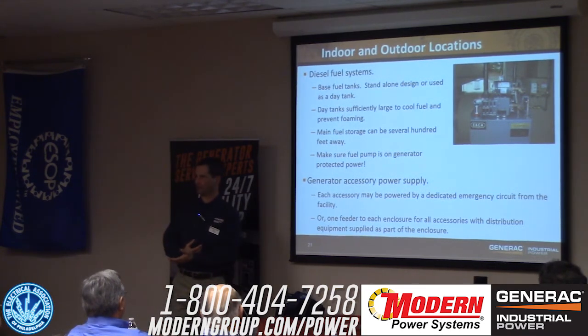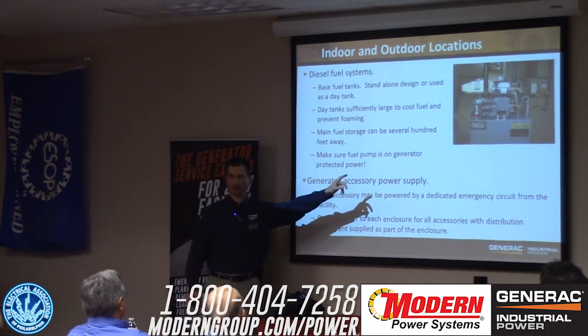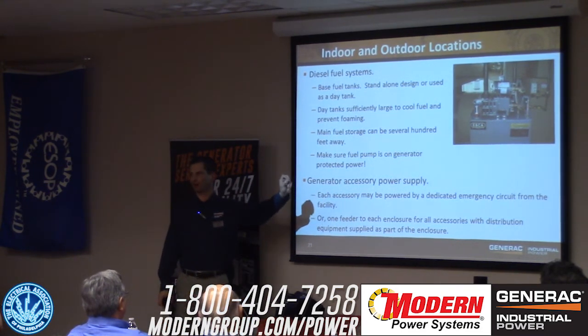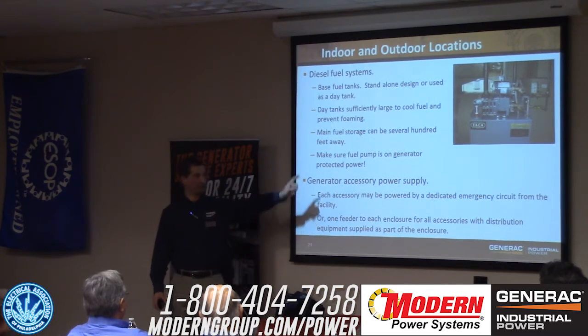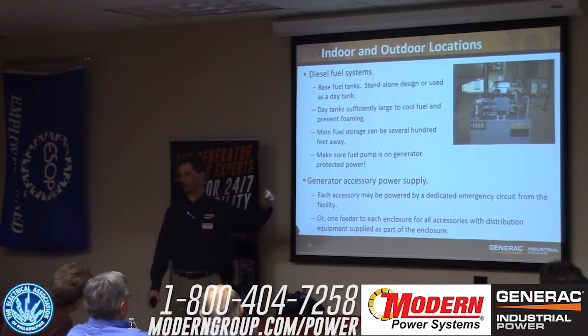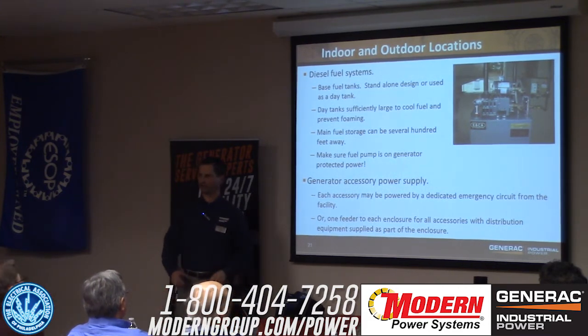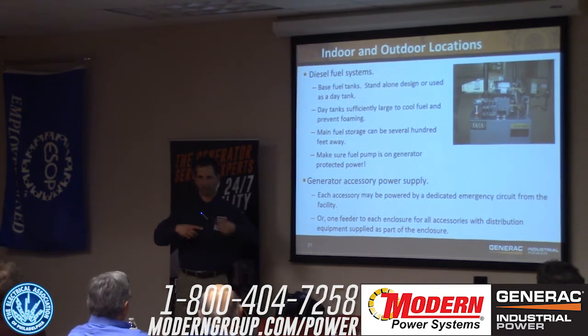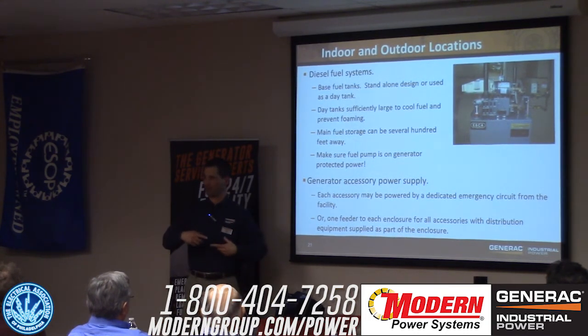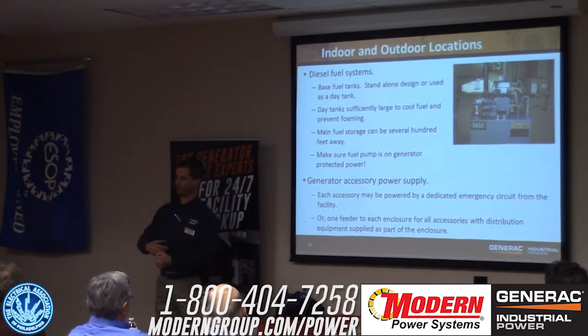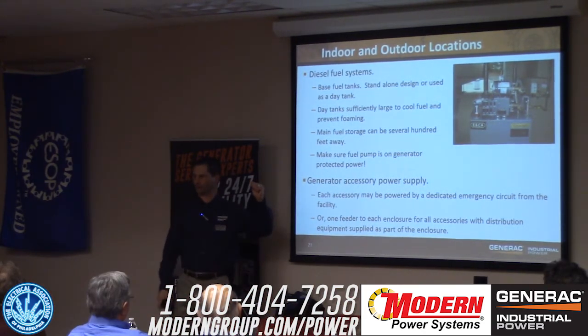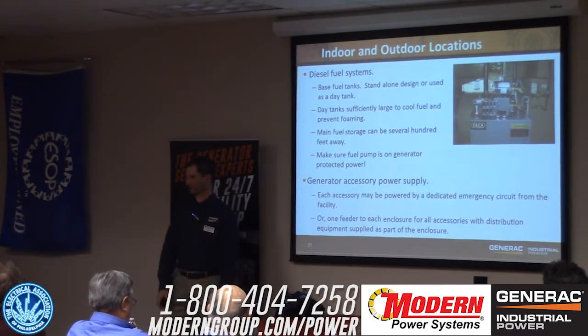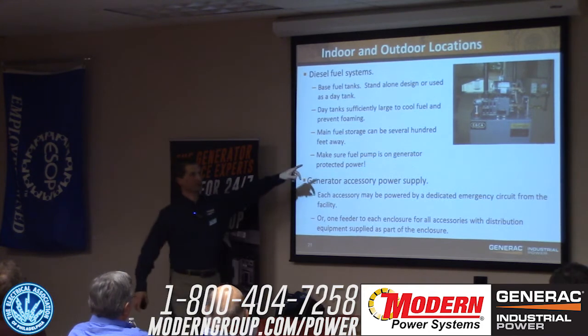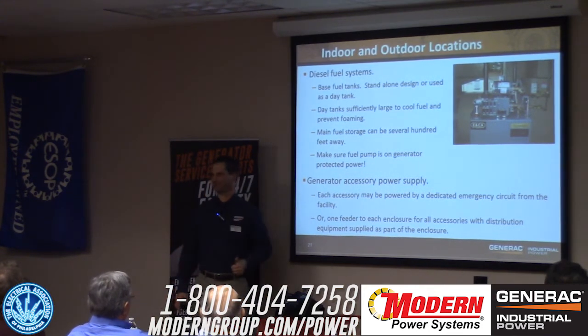If you're going to use a remote tank with a day tank, it's got to have at least 2 hours of fuel in there. So if you've got a 500 kW gen set and it's going to burn 30 gallons an hour, you want that tank absolutely no smaller than 60 gallons because the injector pump in that engine is cooling itself with that diesel flow. So it's circulating that diesel fuel, and a lot of it is being bypassed through the pump, returned back to the tank. If that tank's too small, that fuel's going to heat up. It's going to start to foam. I'm going to start to ingest some air into my fuel system, and then that's it. Engine's going to stop. Okay. Make sure the transfer pump is on emergency power. Had that happen to me too.